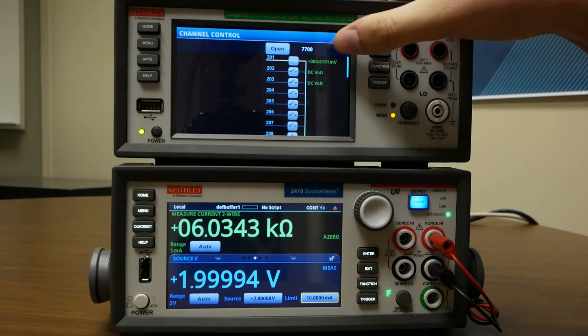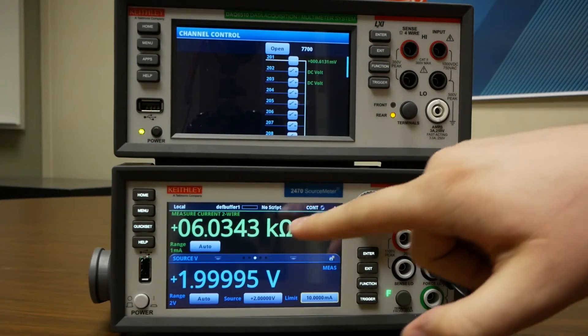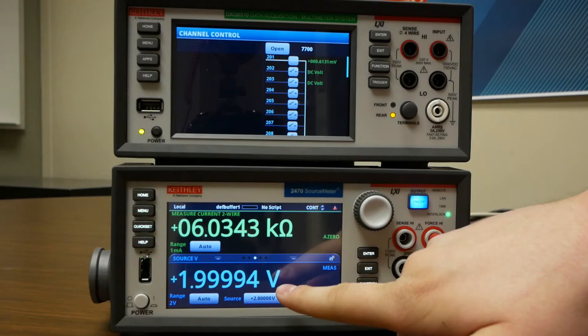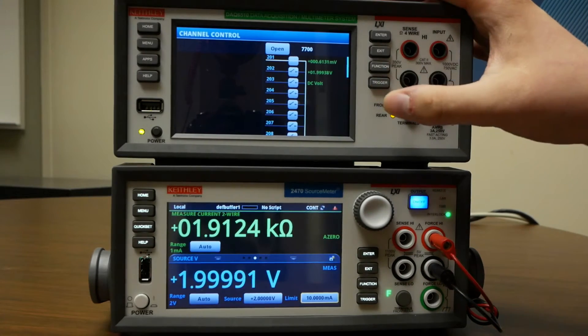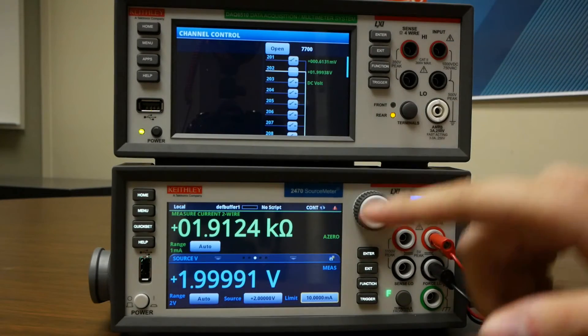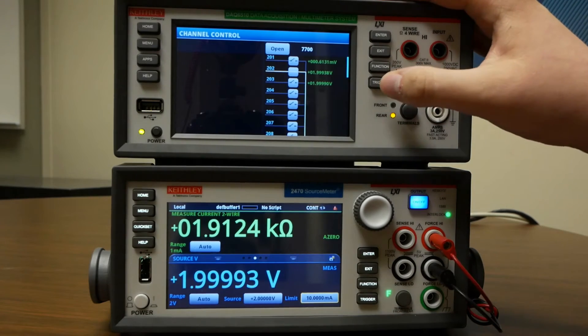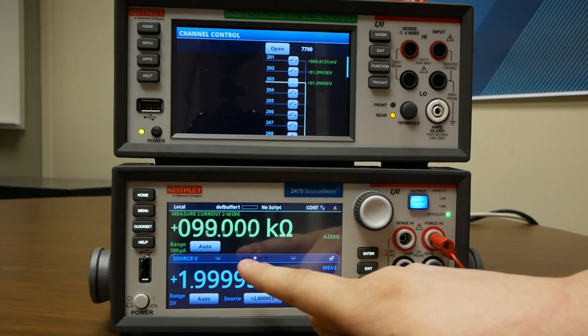When I press the trigger key, we close channel one and we get a six kilo ohm measurement when we're sourcing the two volts. Press it again and we move to channel two with a two kilo ohm measurement and channel three with 100 kilo ohms.